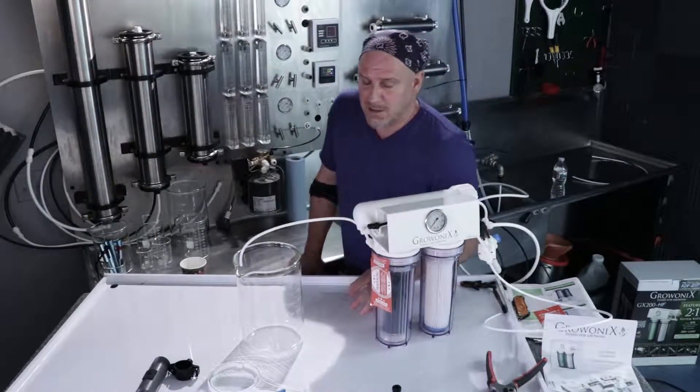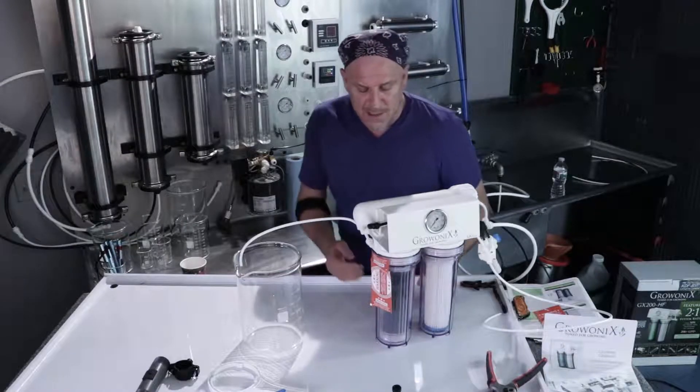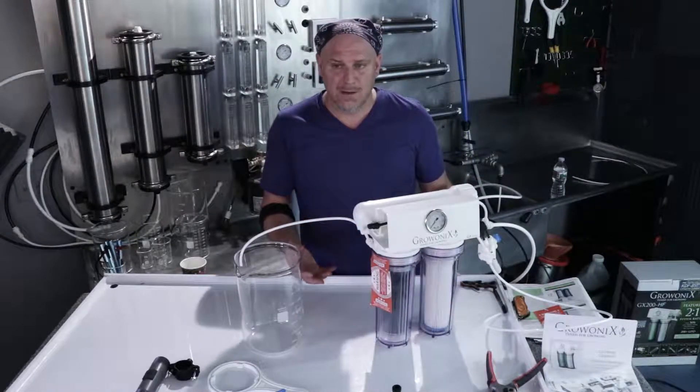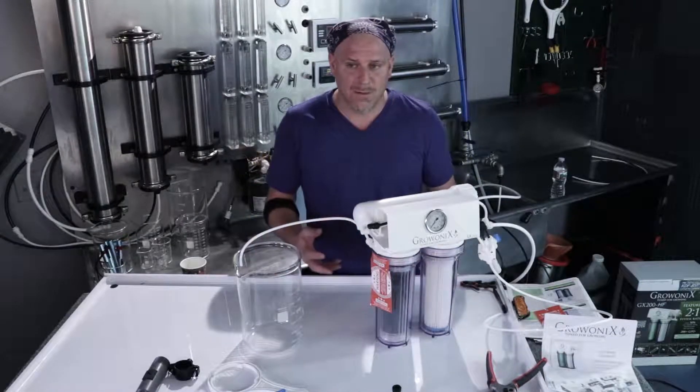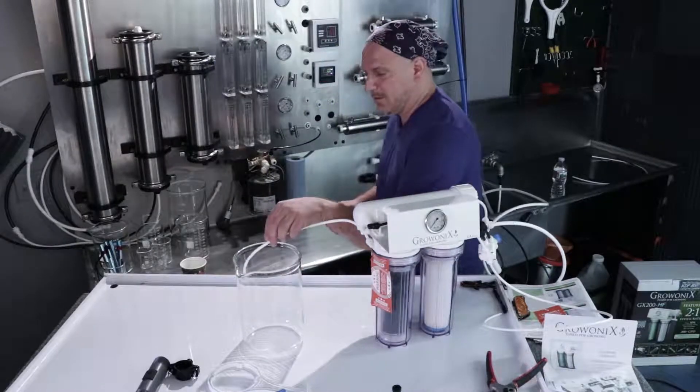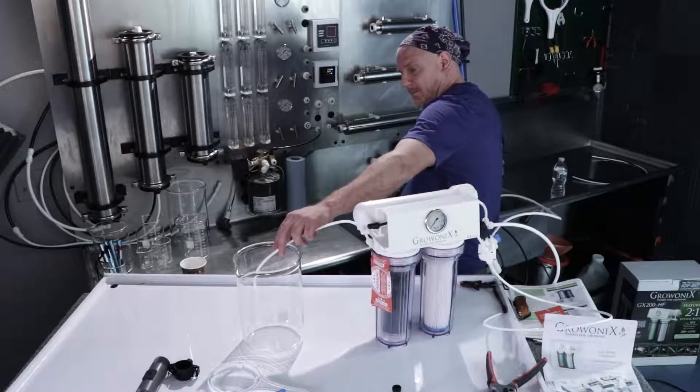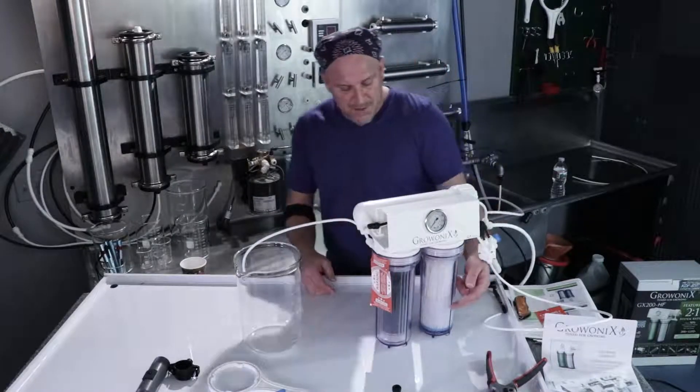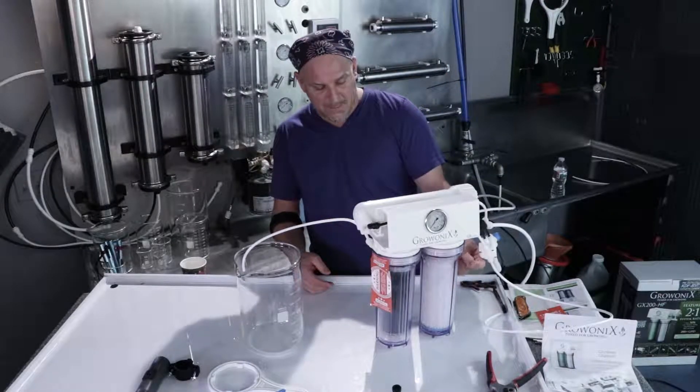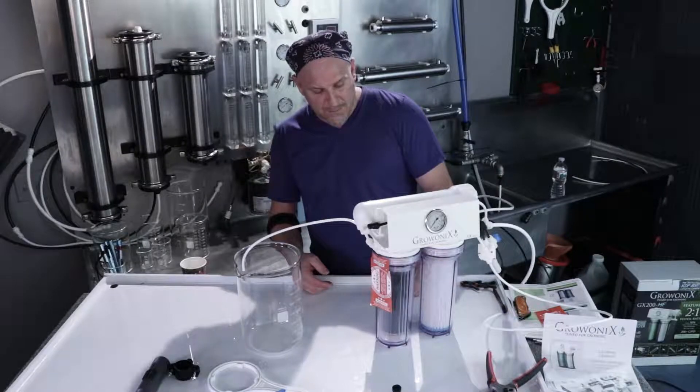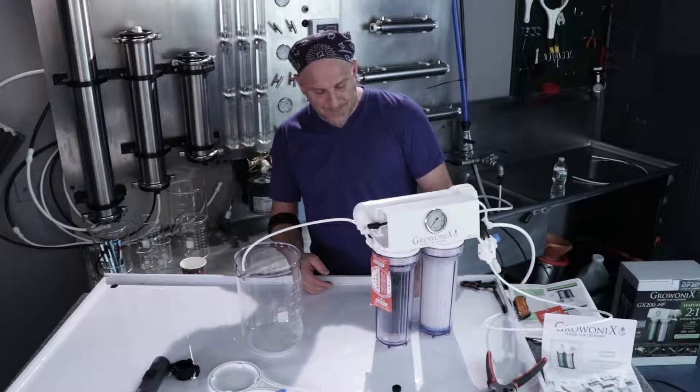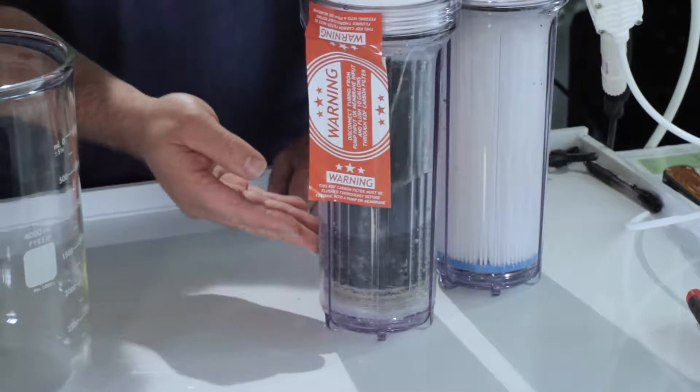We're going to turn the feed water on slowly. Don't blast it. There's a lot of air bubbles in here. We want to bleed out the air and the carbon dust, and if you slam it with water pressure, you could cause a little havoc. So we're going to slowly turn on the input feed water, and you can visually see the water filling up. We're through the sediment filter now, now it's coming up through the carbon filter.